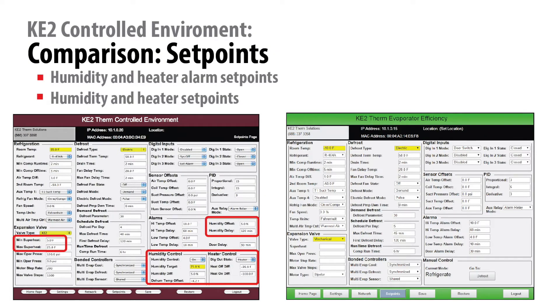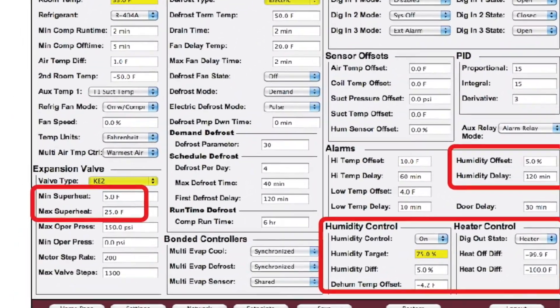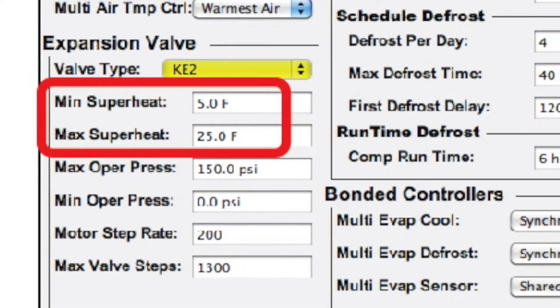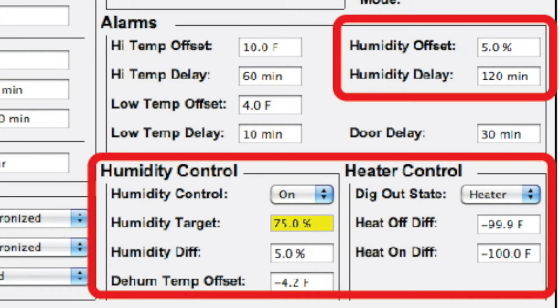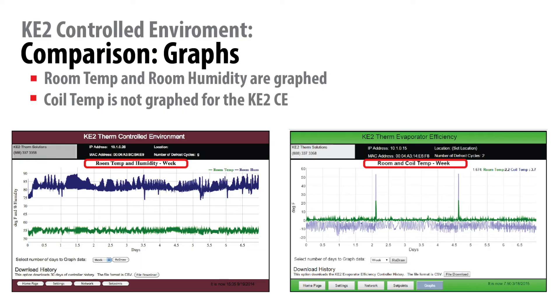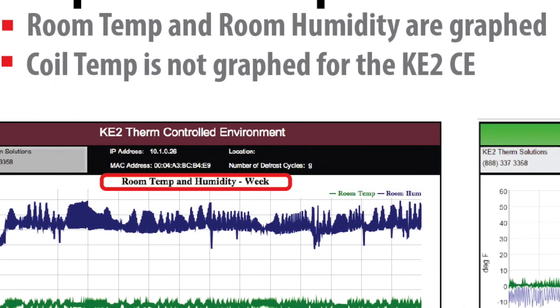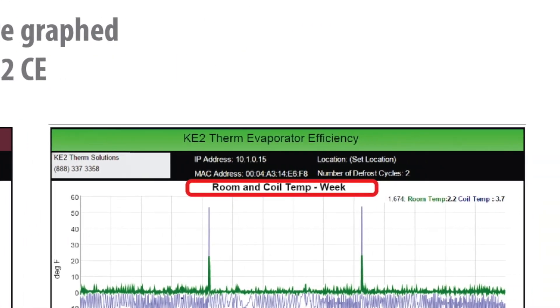On the set points page, you will see three additional set points specific to this controller: the minimum and maximum superheat settings, humidity offset and humidity delay, and humidity control target and optional heater control selection for an external device. Then on the graphs page, notice that the controller graphs room temperature and room humidity values, not coil temperature like the KE2 Evap.